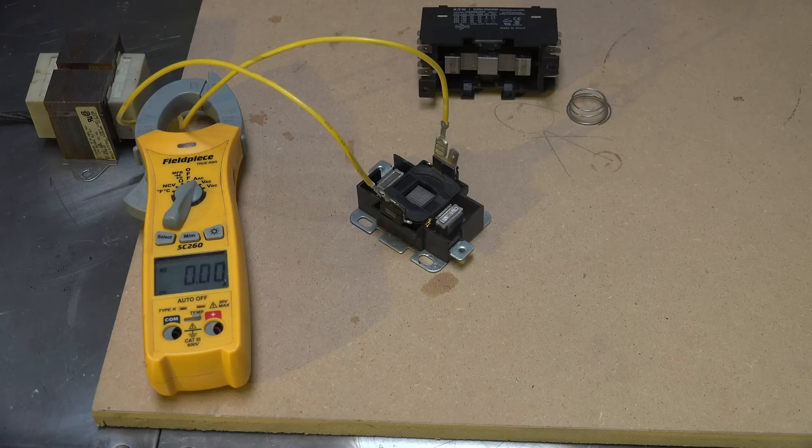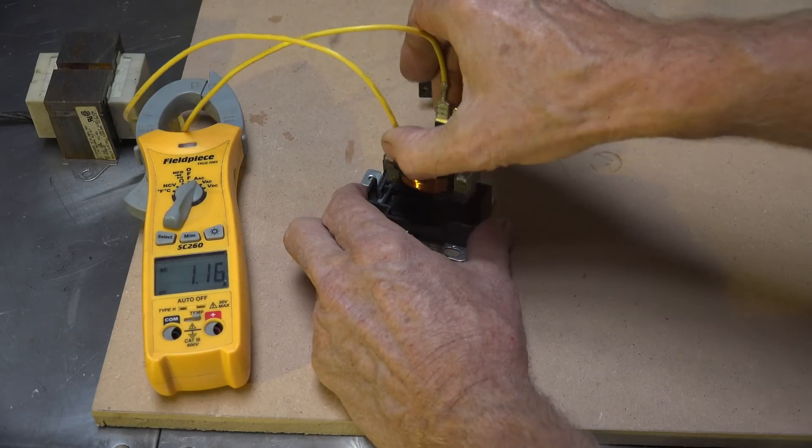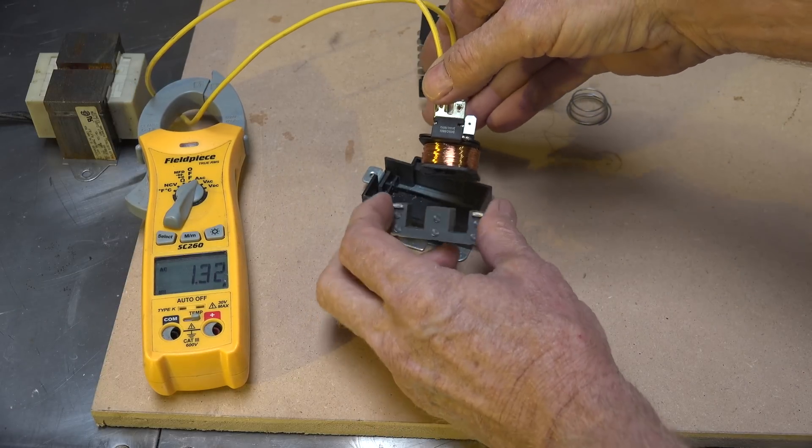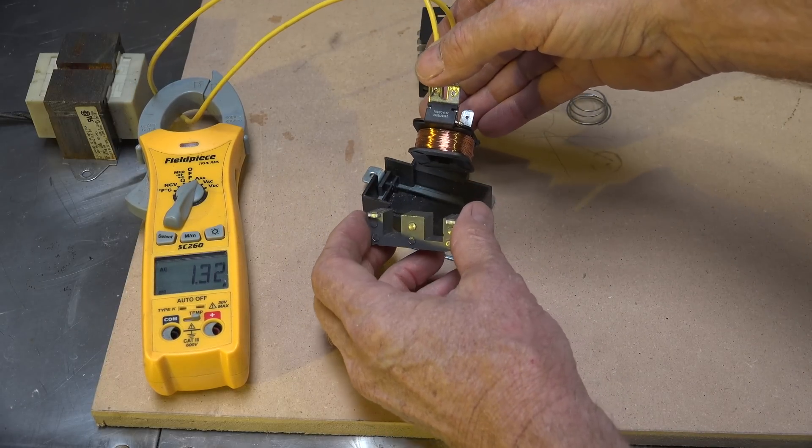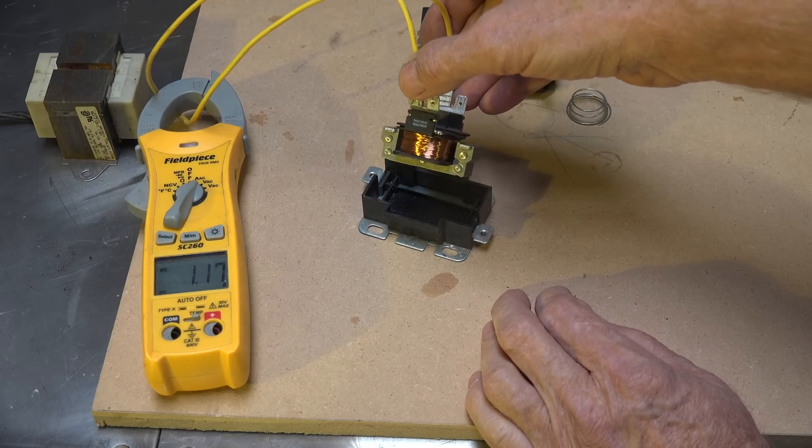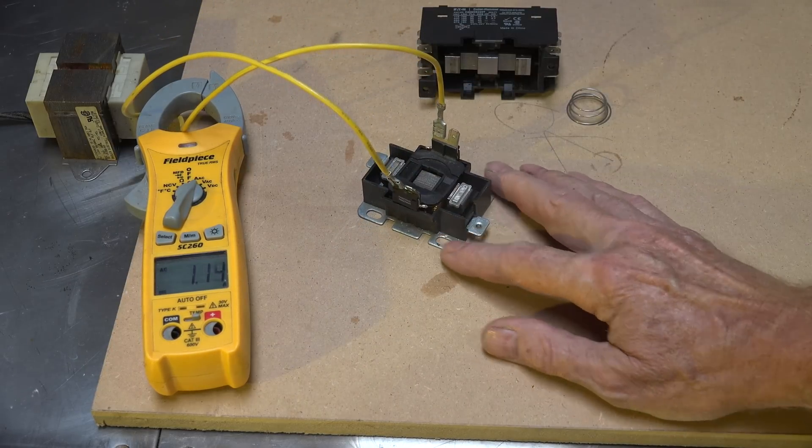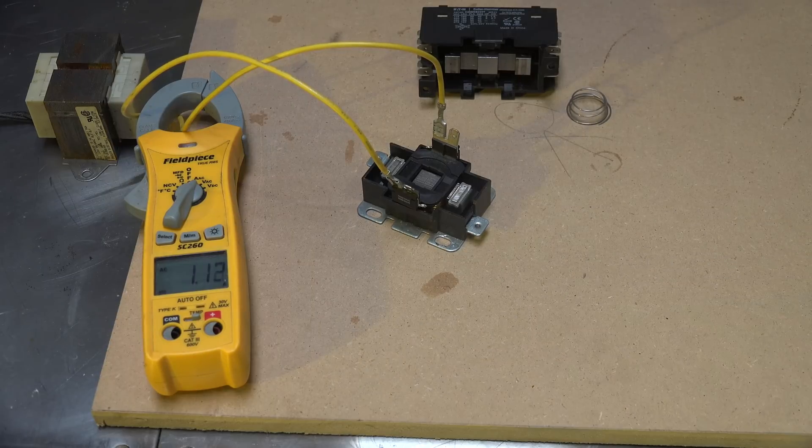Already getting the smell out of this thing because it's about ready to burn up. Let's look a little farther. You can see the amp draw goes up, and it drops some when I put it in there, and it's dropped a little bit more when I put it back in the rest of the cradle.